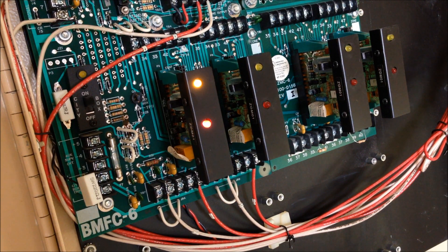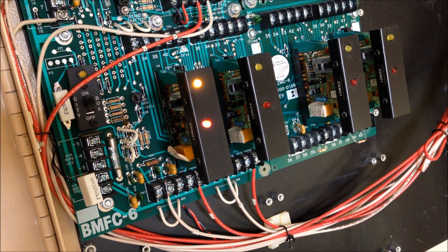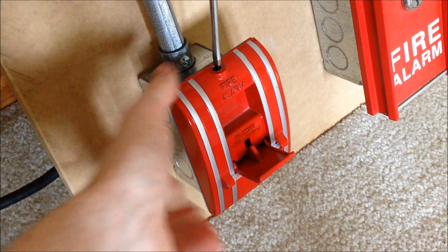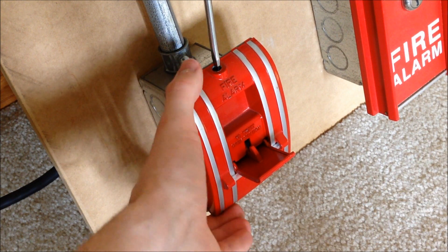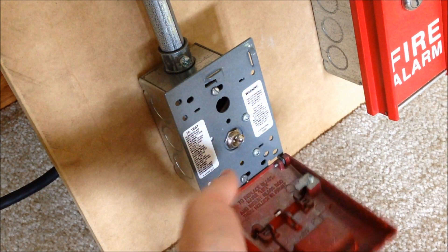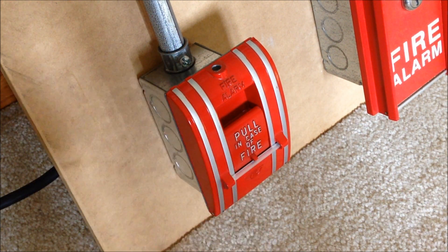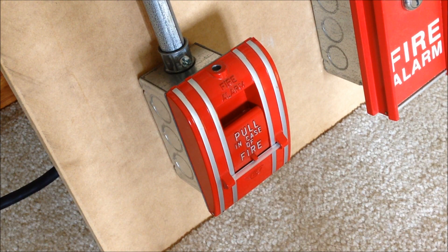Let's go ahead and reset that pull station. Because I showed the MS-6 in the last video along with the i3, there's no real point in activating that today, so we'll just close that one back up and reset the system. On the 270, just insert the screwdriver on the top, reset the switch, and close it back up. This break rod here is just a tube from a pen, so it just bends out of the way when the station is activated, which is why it didn't shatter all over the carpet.